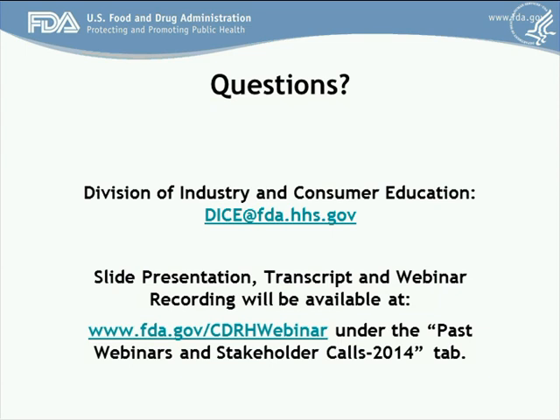Okay, great. And a second follow-up question. As I understood, this was applicable mostly to new products that are being submitted for 510Ks and considered for 510Ks. Products that are in the market already that are potentially just getting updates wouldn't be subject to it unless they're being refiled for a new 510K submission. Is that correct? I'm not distinguishing just getting updates versus a new 510K submission. If you have a product that's on the market that requires a 510K because of changes you've made, it would be up to the discretion of the review branch to see whether cybersecurity risks need to be concerned or whether the device as it stands alone poses low risk, and so the modification you propose could go through without addressing cybersecurity.